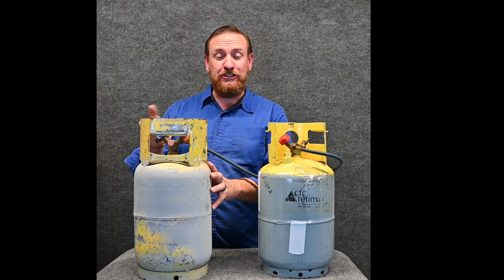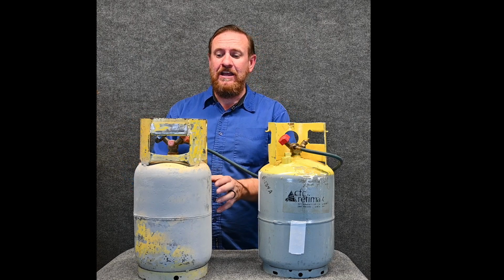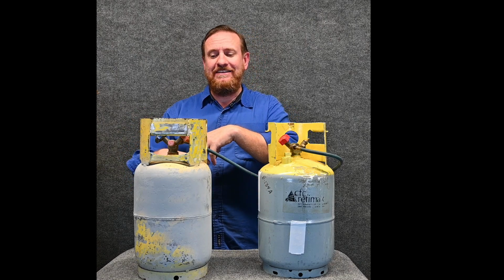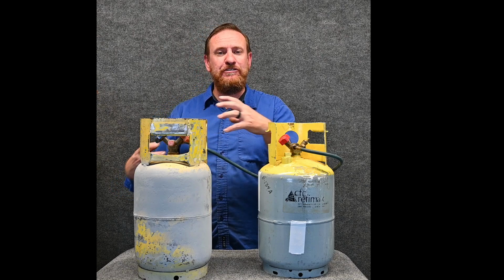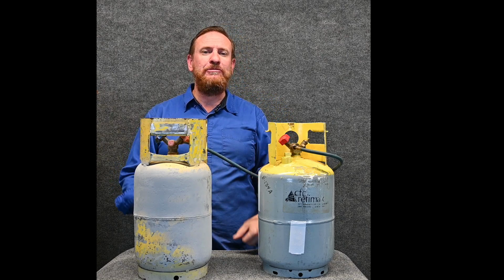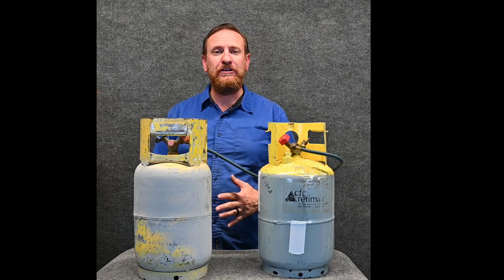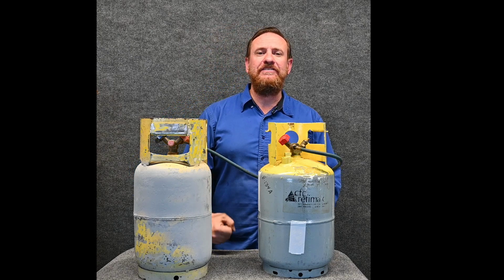So if I was to shut the pump off and take this outside, since it's completely full of liquid, as the temperature started to increase, the refrigerant would start to expand and it could potentially become a bomb. So refrigerant migrates to the cooler location. That's important. Let's apply this to the next thing I want to talk about.